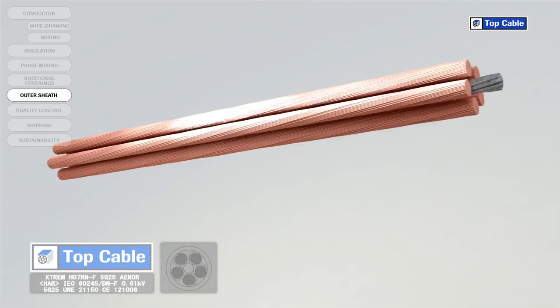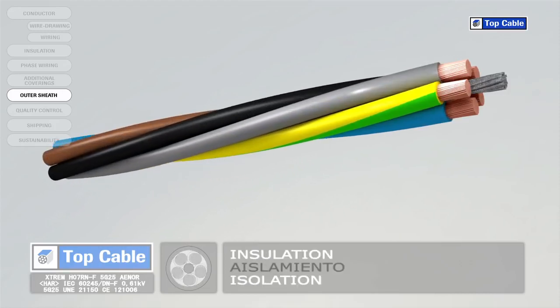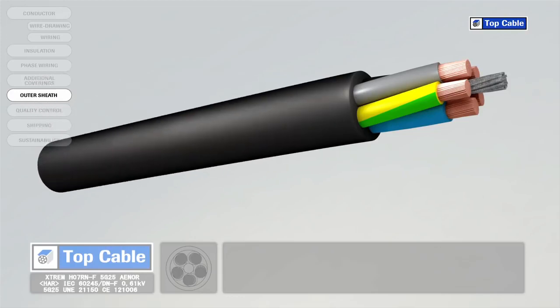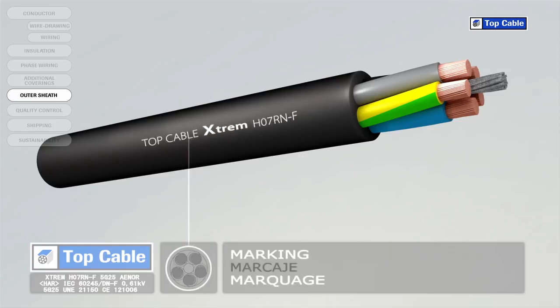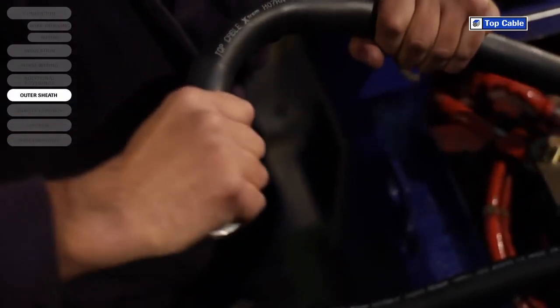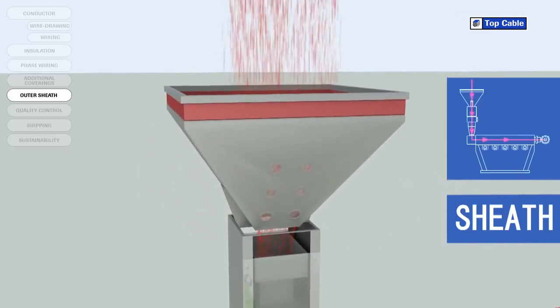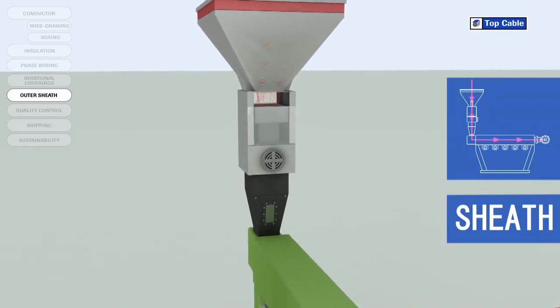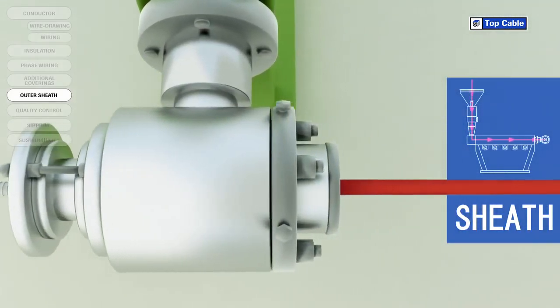Cables usually have an outer polymer covering for protection. This is called the outer sheath. The sheath protects the conductors and their insulation from external elements which may change their electrical properties, such as moisture. It also protects them from mechanical aggression, which may occur during the installation of the cable. As with the insulation, the outer sheath can be made from a thermoplastic or a thermosetting plastic. The outer sheath is applied like the insulation via a process of extrusion at high temperature. The sheath may be made from different materials depending on the required protection level, the final flexibility of the cable, the work environment, etc.